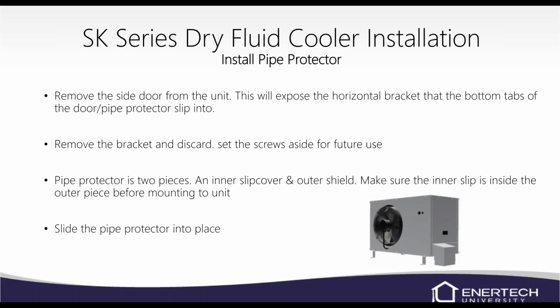But in order to install this pipe protector, if you look at the picture on the lower right there, that little box sitting towards the bottom of the unit is your pipe protector. So you're going to remove the door. It's got the little handle on there right above that protector, and it's going to expose the brackets that the bottom tabs of the door and the pipe protector slip onto. Doesn't take a rocket scientist to get those tabs lined up. They'll line up pretty good.